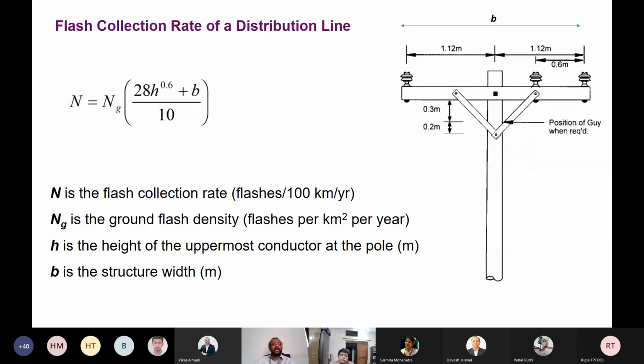So this is a very popular equation to calculate the flash collection rate. N represents how many flashes the medium voltage line will collect per 100 kilometers per year. Ng is the ground flash density, H is the height of the uppermost conductor of the pole, and B is the structure width. You can see here that B is measured between the outermost insulators of the power lines.